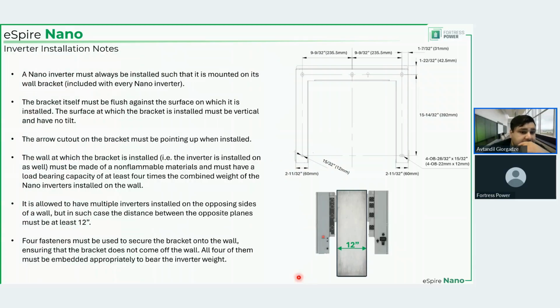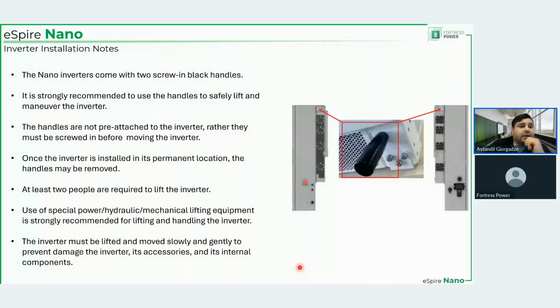What else? Yeah, no tilt that I mentioned already. I think we went through all of these. Now, these are the handles that I was talking about before. And as I said, those are screw-in handles. Actually, if you're using a crane or something of that sort, you can also use these handles because there are no separate crane attachment points on the inverter. But always do use care when moving the inverters around. No sudden movements, no dropping it, and always please stay safe when you are maneuvering the inverter.